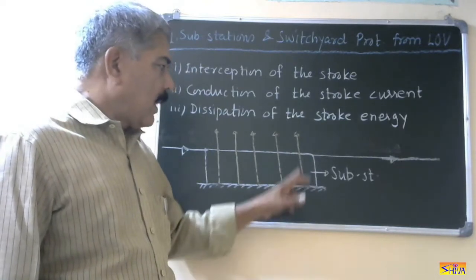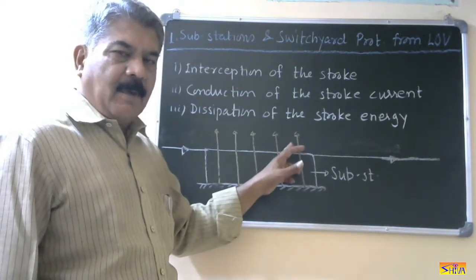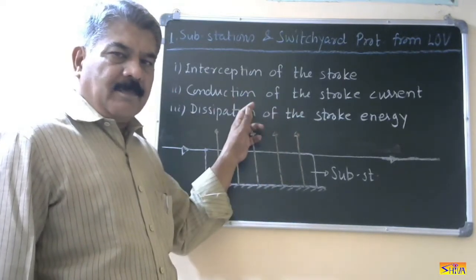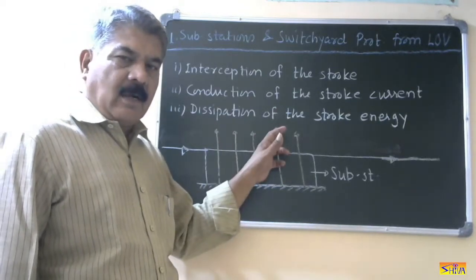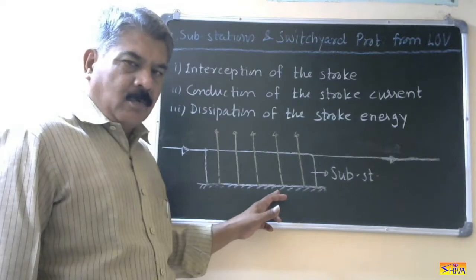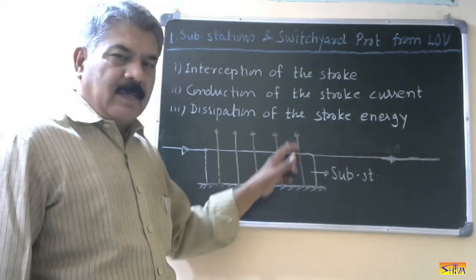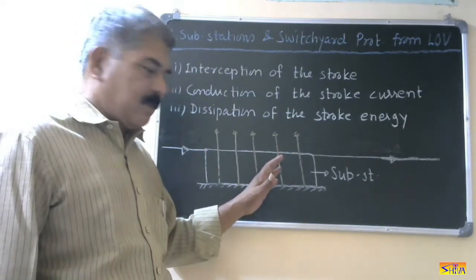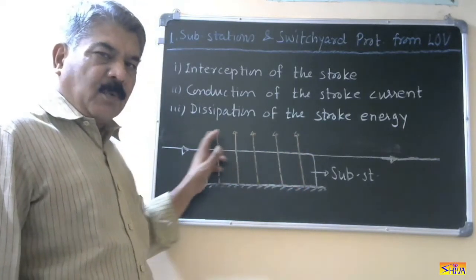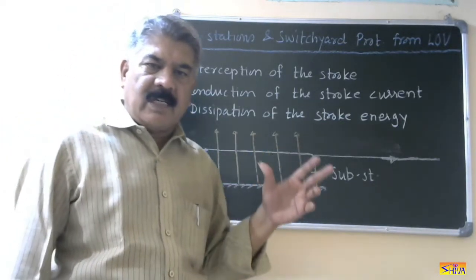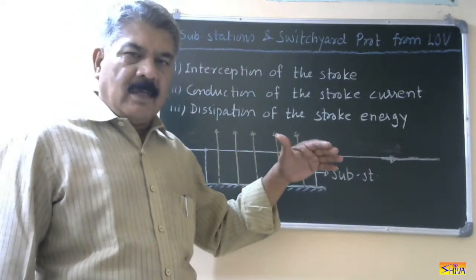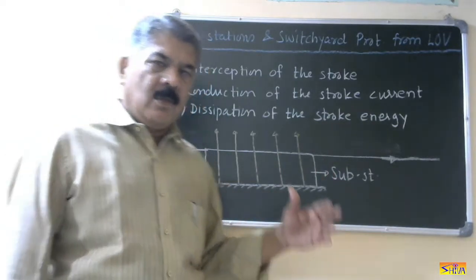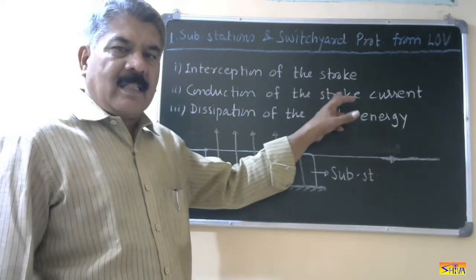These metallic objects are connected to ground and have sufficient height compared to the power system equipment. If there is a lightning cloud overhead, these objects will attract it and discharge the lightning overvoltage. So either metallic objects are installed at regular intervals, or the entire substation is provided with electrostatic shielding — installed at sufficient height and covering the entire substation or switchyard — so they intercept or attract the lightning stroke.